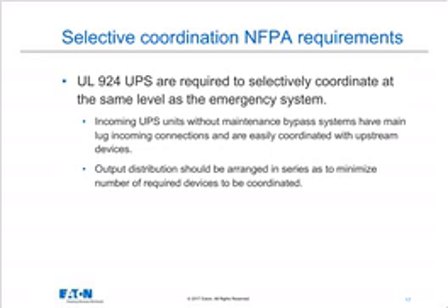So the UPS would be connected to a dedicated panel, and that panel would feed, let's say, 5% of the existing overhead light fixtures in that office building, which means when utility power goes off, all the lights go off except the ones that are powered by the UPS. So they are chosen in advance to be the ones that will light the hallway, provide lighting in the restrooms, even in elevators and things like that, so that people have a way to visibly see how to exit the building. The good news is I'm going to wire up those lights anyway as a part of the building lighting system. The only difference here is I'm feeding my emergency lights with a UPS and a dedicated panel that handles just emergency lighting.